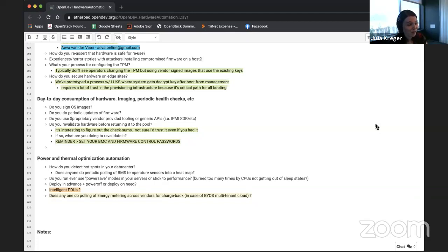Well, I'll go with what I did years ago, which was I just kept the thresholds on the out-of-band sensors ridiculously low. So if air intakes hit like 90 or 80 or something like that, I don't remember exactly what it was, then I would get a warning. I wouldn't actually have that warning trigger a page, but it would give me enough information if I loaded the status console and go, oh, I've got 6 machines in this rack that are warmer than the rest of the data center. I should probably go look at that and actually reevaluate the airflow.